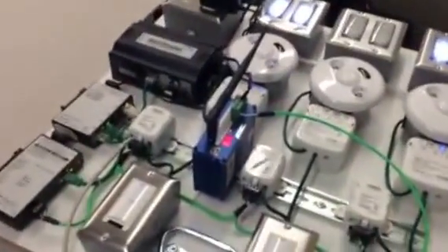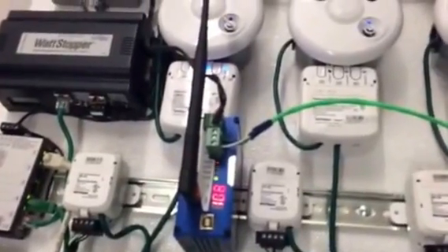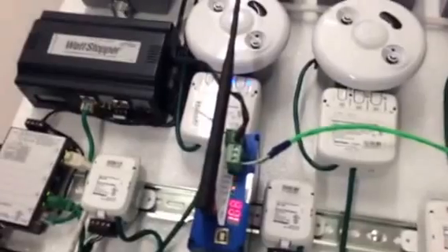Down here at the bottom is where he's got control of the DLM networks. 2 of these rooms are in the building that we're hardwired to, and that third room over there is actually connected to the remote building. So let's go over there and take a look at that. And Elliot, what I'd like for you to do is start to use the trunking capability, the wireless trunking, the second technology that we're demonstrating here. This RF transmitter just takes the BACnet messaging off the MSTP wire and puts it on a virtual wire or an RF transmission over to a remote building.